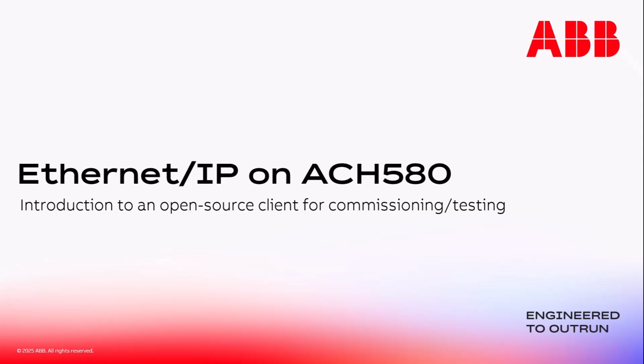And so you might ask yourself, when might this be useful? In an application startup, for example, very often the VFD may be commissioned before the controls contractor is on site to start up the building controls. In this scenario, since you're already there commissioning the drive, it's useful to have an option to pre-configure the drive with its intended network configuration and then confirm its operation without requiring the building controls to be operational.